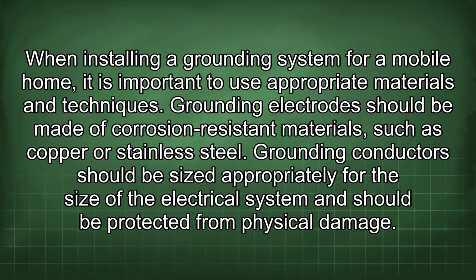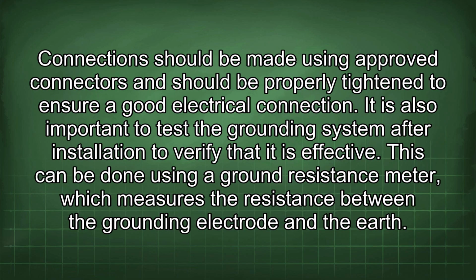Grounding electrodes should be made of corrosion-resistant materials such as copper or stainless steel. Grounding conductors should be sized appropriately for the size of the electrical system and should be protected from physical damage. Connections should be made using approved connectors and should be properly tightened to ensure a good electrical connection. It is also important to test the grounding system after installation to verify that it is effective.